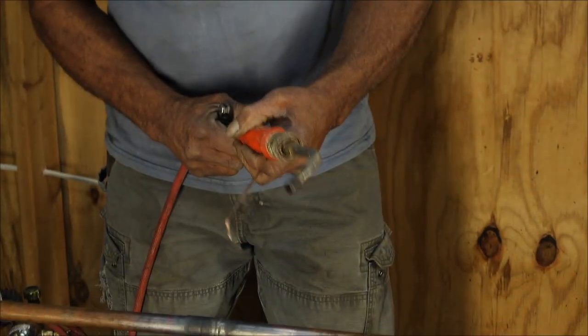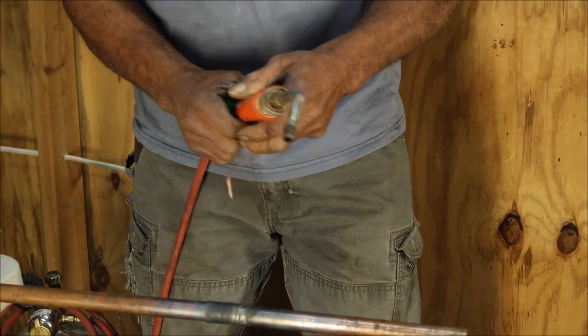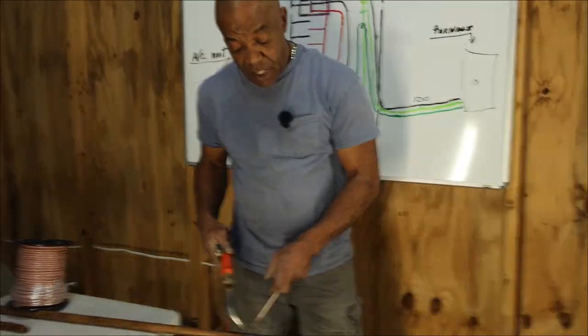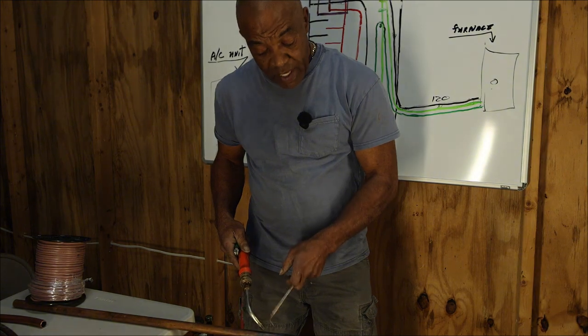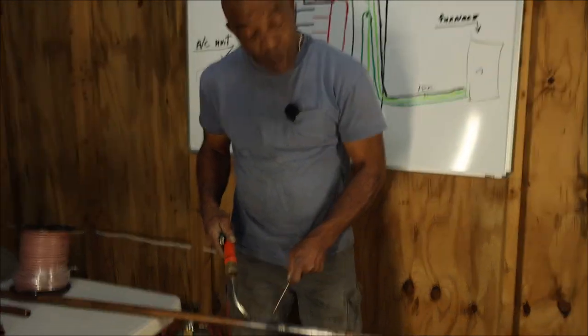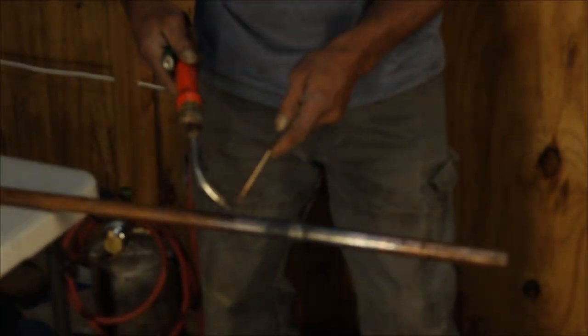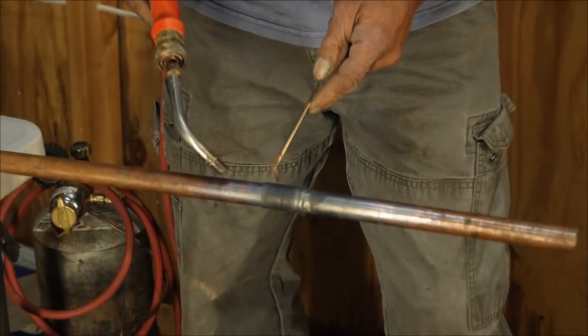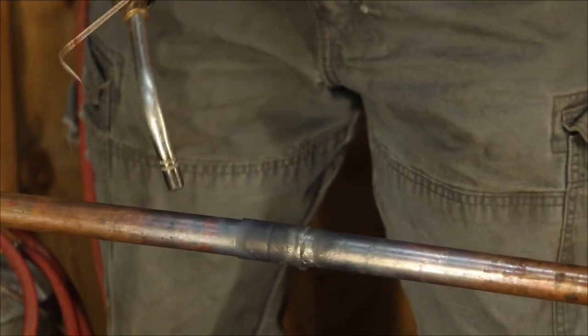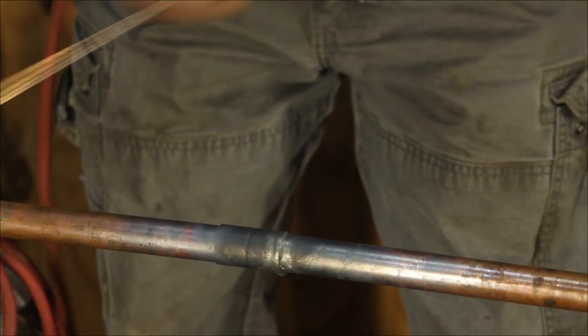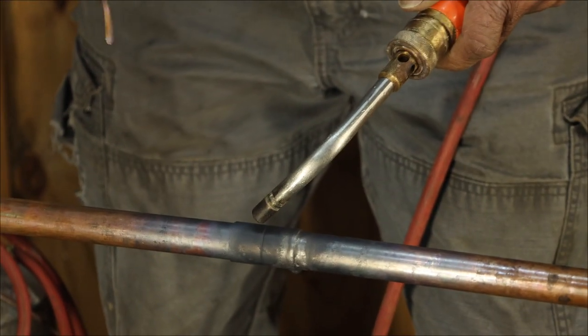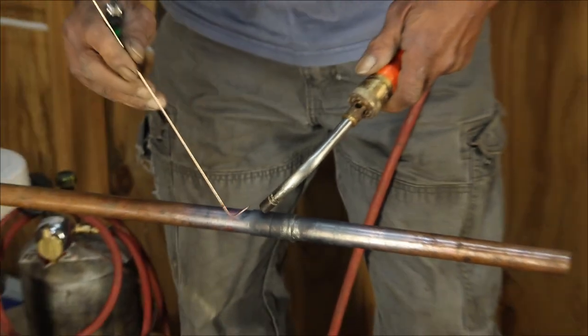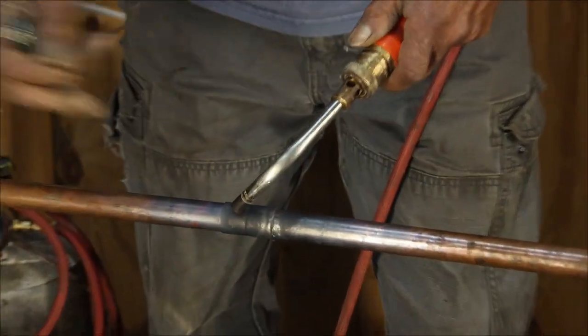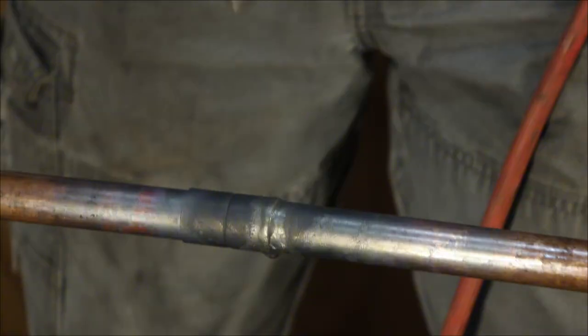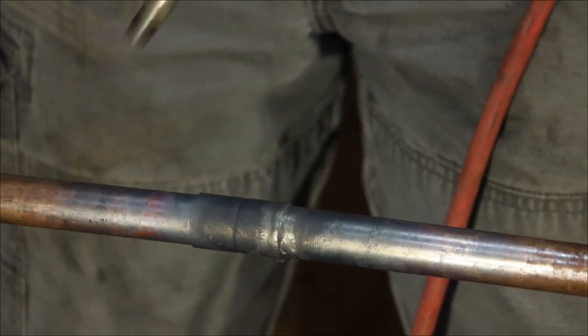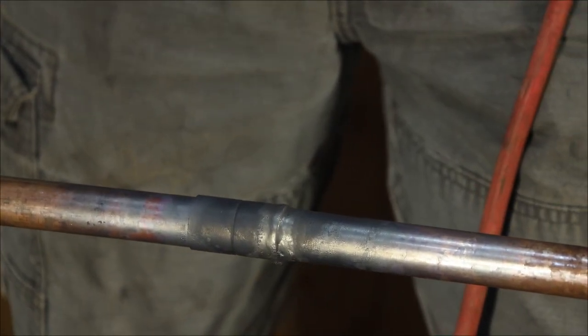Let's braze the other side. The same technique. I'm going to heat the copper until it gets hot enough to melt the brazing rod. But at the same time that I'm heating the copper, I'm heating the coupling. Then I'm going to move my heat to the coupling so that as I apply the brazing rod, the heat will draw the brazing rod into the connection, okay?